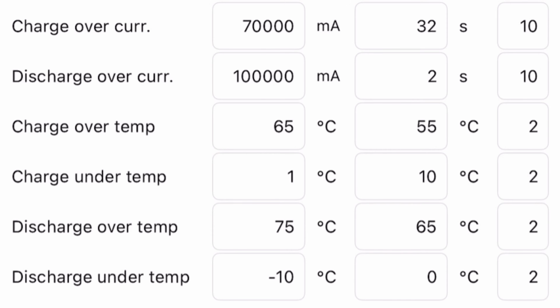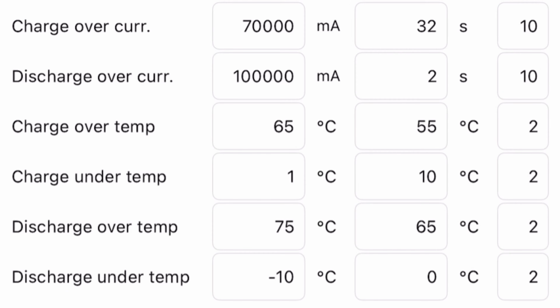So the temperature cutoff part. Now this is important. The batteries will not charge if it is greater than 65 degrees centigrade, and they will not charge if they're colder than 1 degree centigrade. Now that's when it cuts off. It'll turn back on and let them work again if the temperature comes down to 55 degrees centigrade or up to 10 degrees centigrade. The reason is, if you exceed 65, the cells can burst into flames. I believe 65 is like 160-some degrees Fahrenheit. You just don't want to go there. And then the cells can't go less than 0. At 0, they shouldn't be operating, which is why I have it cut off at 1 instead of at 0. Now, if it's the dead of winter, warm your boat. If your boat's warm, your batteries are warm.